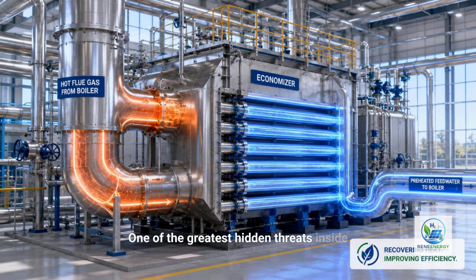One of the greatest hidden threats inside any boiler is oxygen dissolved in the feed water. Even tiny amounts can cause corrosion, shorten equipment life, and reduce system reliability. The deaerator removes dissolved oxygen and other non-condensable gases before the water enters the boiler. Using controlled heating and steam contact, unwanted gases are separated and safely vented away. By protecting the boiler from internal corrosion, the deaerator helps ensure decades of reliable operation while reducing maintenance costs and preventing unexpected equipment failures.